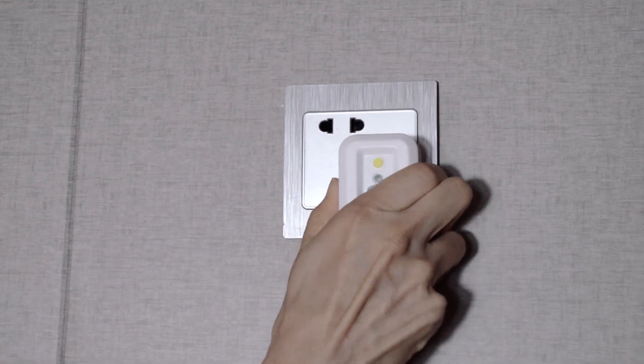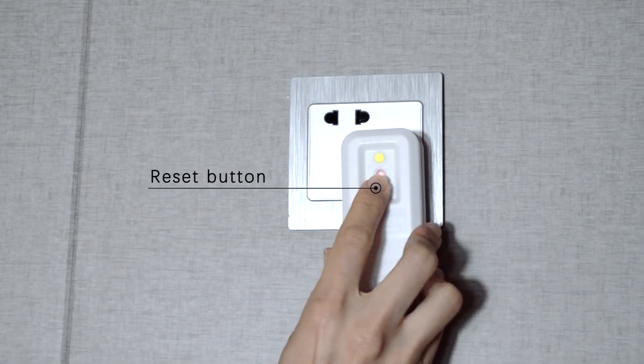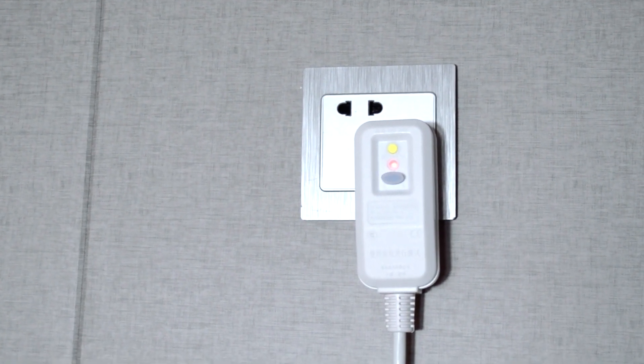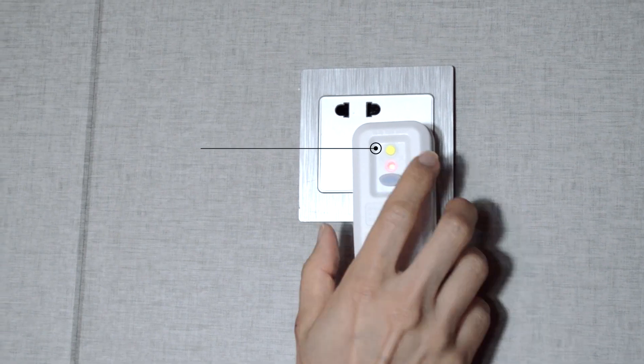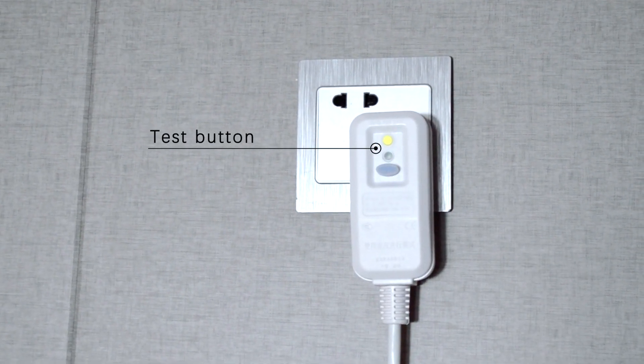Connect the leakage circuit breaker to a power socket. Press the reset button. The yellow and red lights turn on, which indicates the device is powered on. Press the test button. The yellow and red lights turn off, which indicates the protection is on.